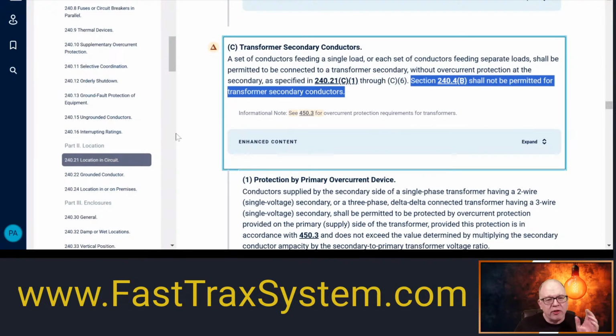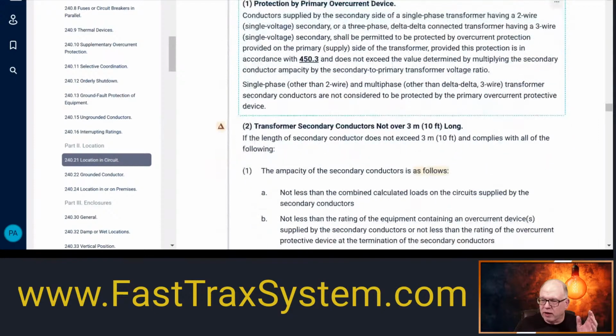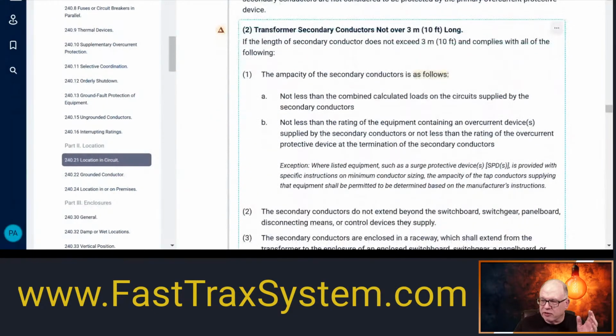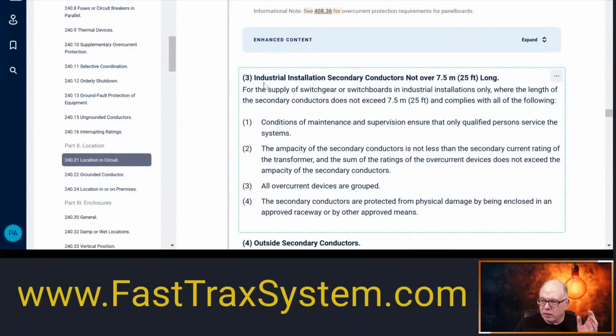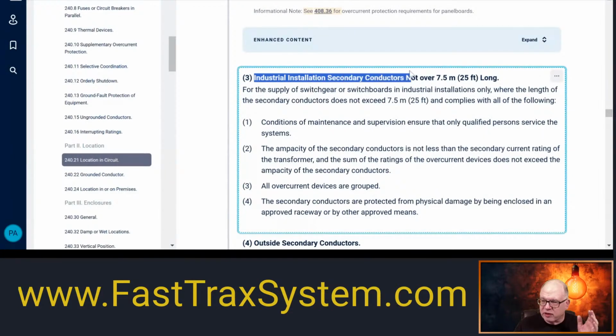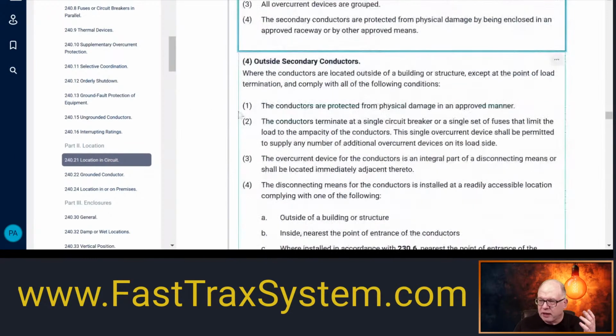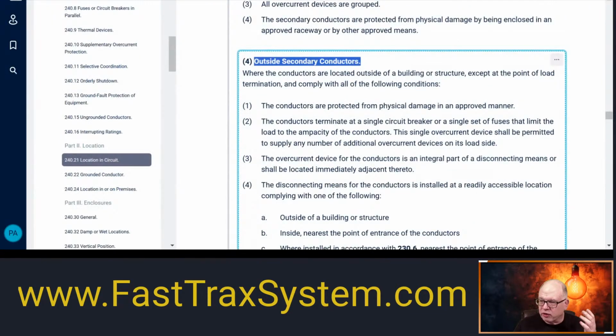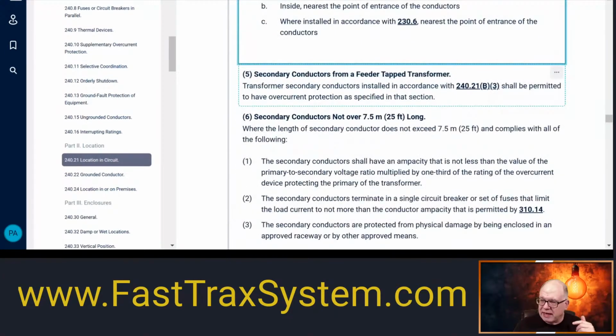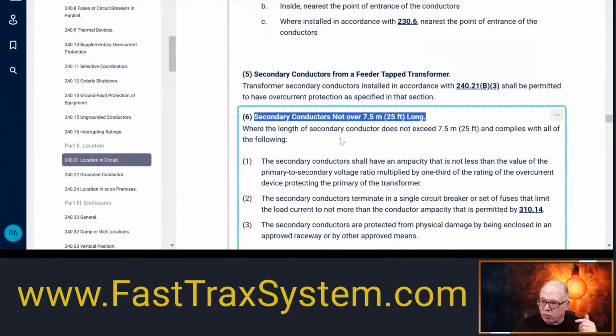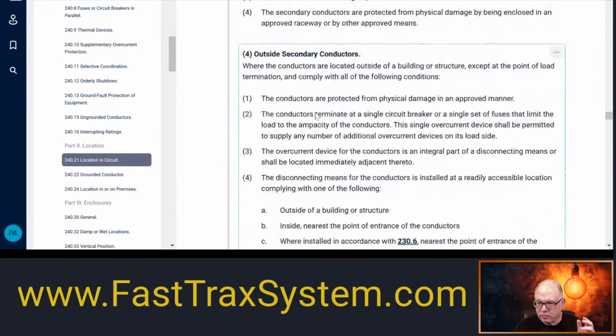Now, we're going to have other episodes where we talk about where the secondary conductors can be, let's say for an industrial installation, not over 25 feet, so you can go 25 feet. We have outside secondary conductor rules, which are unlimited because they're outside, so we don't have a length limitation on them, not inside. And then, of course, you'll have other types of applications that we'll be talking about. Secondary conductors not over 25 feet will be the next episode, when we talk about the 25-foot secondary conductor rules, that type of thing. Okay? So let's see here.